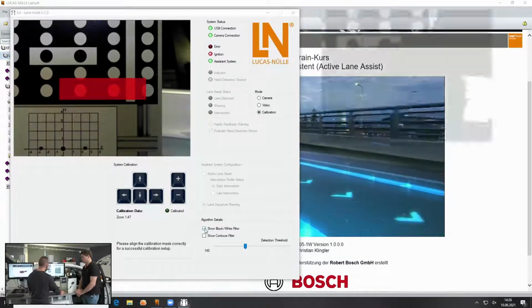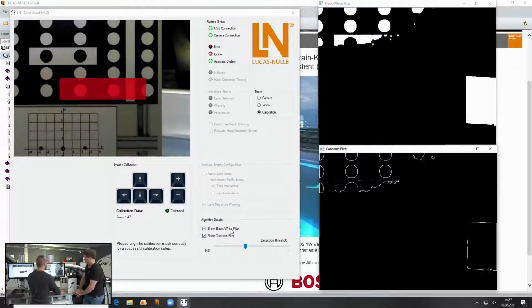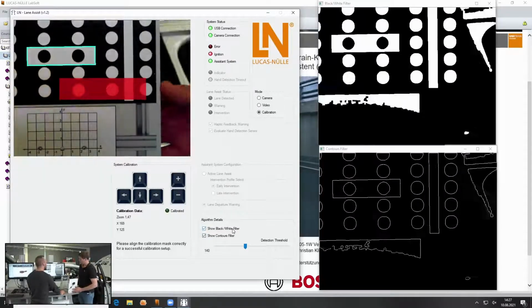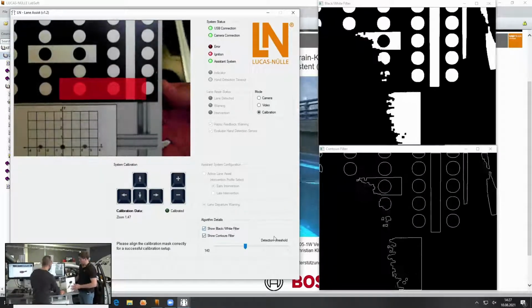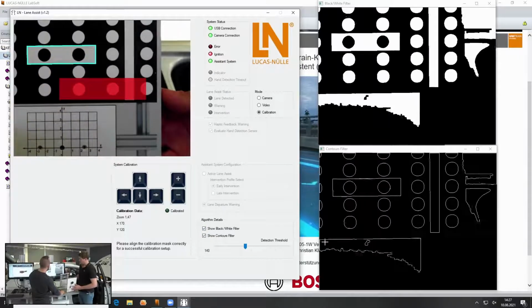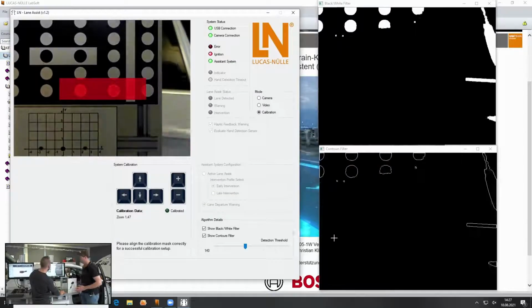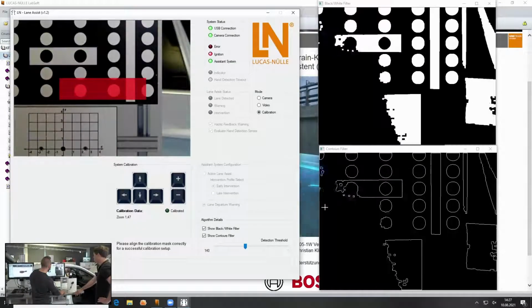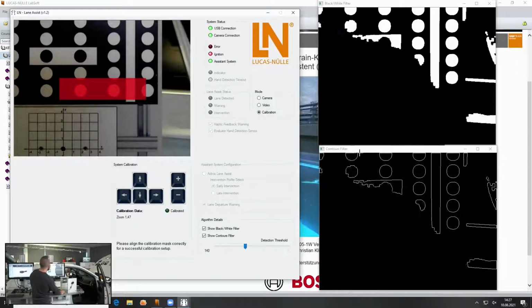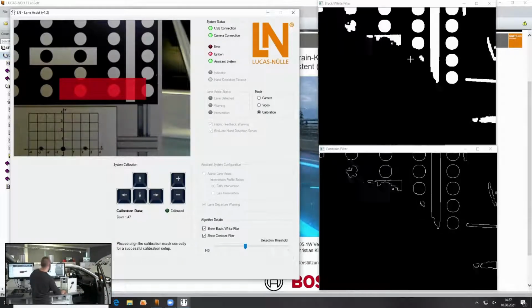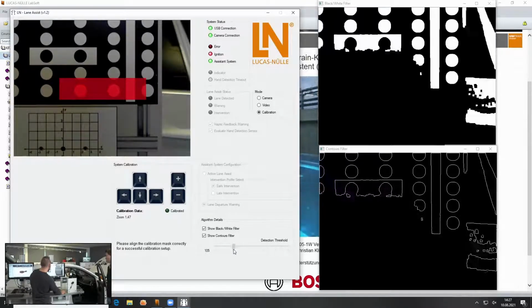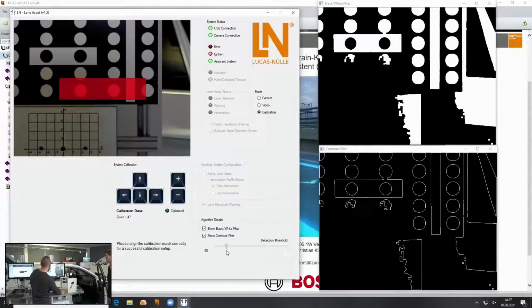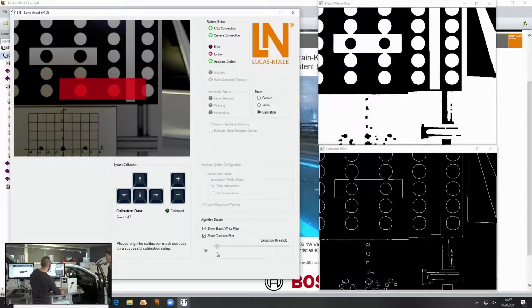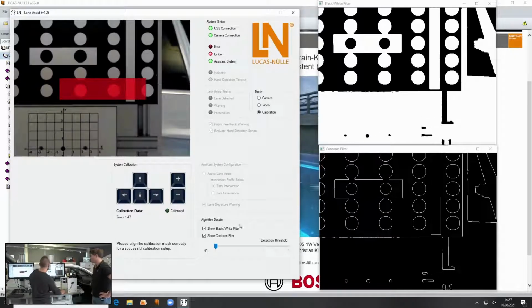So one very important point is the recognition of the light. So how much light is going into the camera. And as you see here, nothing is simulated, that's all in real time. But we have right now a problem that the camera cannot interpret exactly. So Daniel is moving in there. There you see it can't really understand the picture because there's too little light. So what we have to do now, we have to increase the light or the sensitivity which comes into the camera. And there we see now suddenly how it detects the calibration target now in the filter as well.